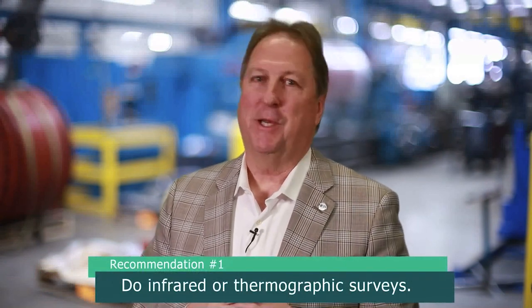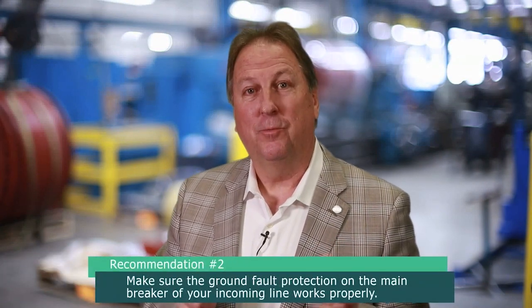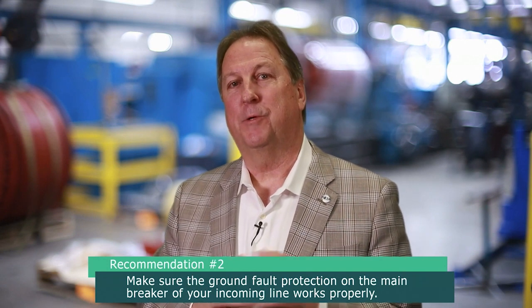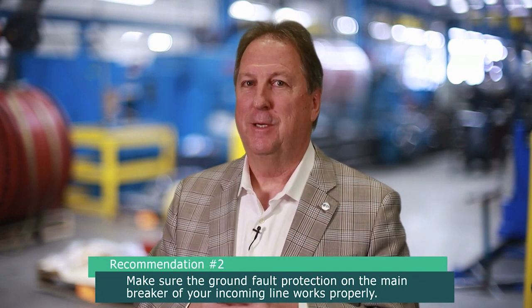So Kevin, I mentioned in the beginning, what are the two most important things you can do? Do an infrared survey every year, because you know what that does? It protects you from fires. The other thing I said was make sure you test your ground fault protection system, because you know what that does? It protects you from fires. Those are two very simple and very important things when it comes to electrical maintenance.